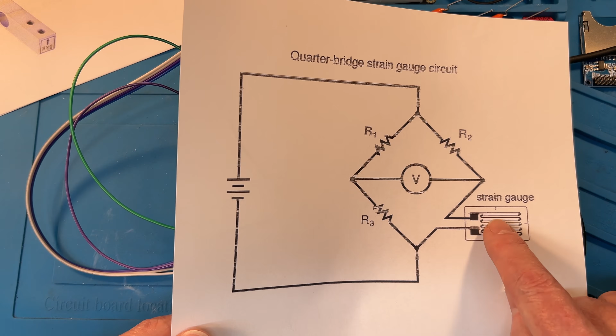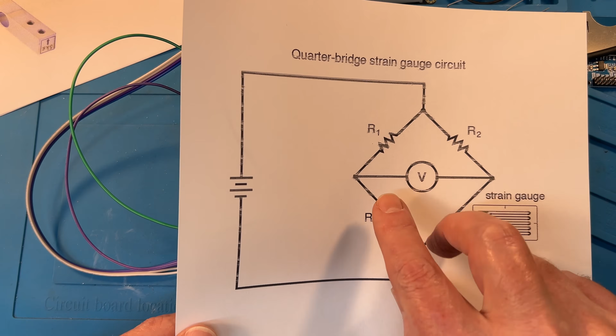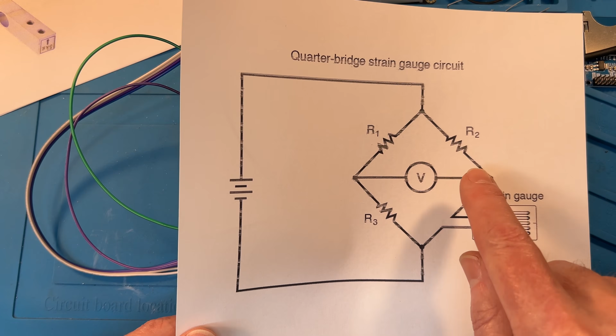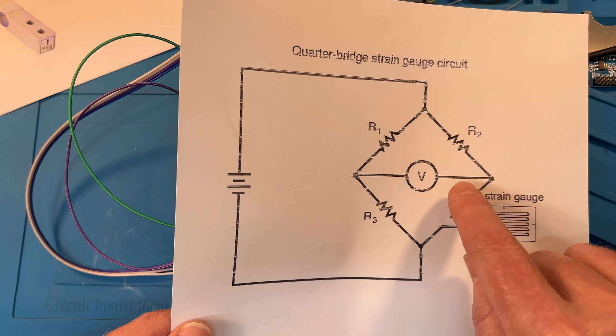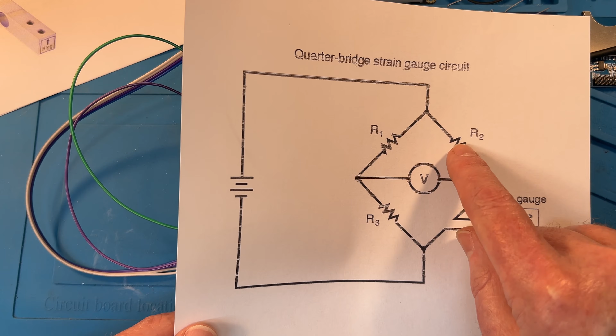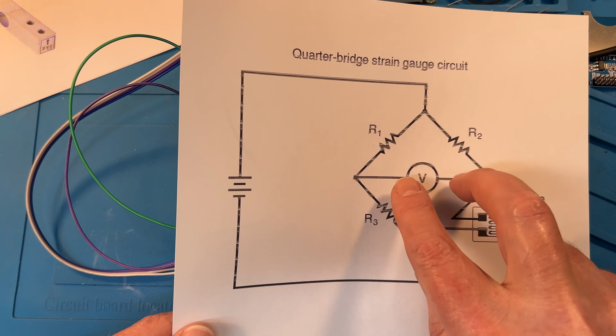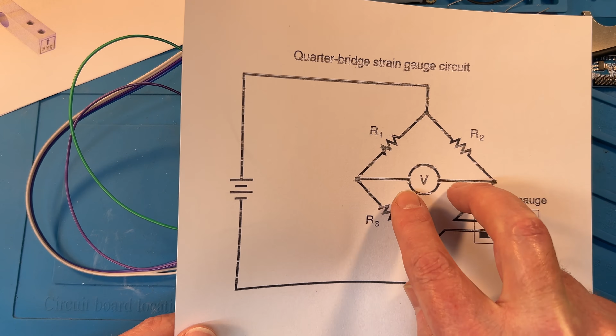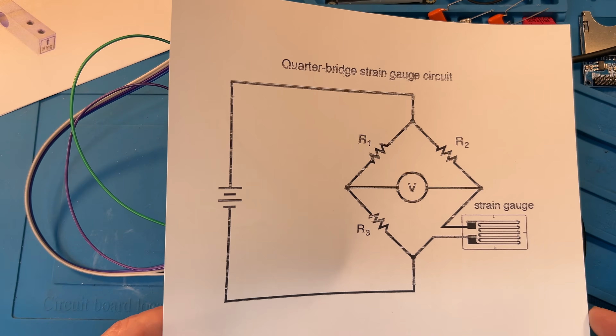So what happens is, when there's no load on the strain gauge, these 4 resistors are the same value, which means that the potential difference between these 2 points is 0. When you change the resistance of this, the strain gauge or this bridge is no longer in balance. So this voltage with respect to that one is shifted. So you've got a potential difference between these 2 points, and that's what you're measuring. It's in the order of microvolts to millivolts, which is why you need a very sensitive amplifier to amplify these signals. So this over here is a 24-bit A2D that's reading this microvolt signal out from this load cell.